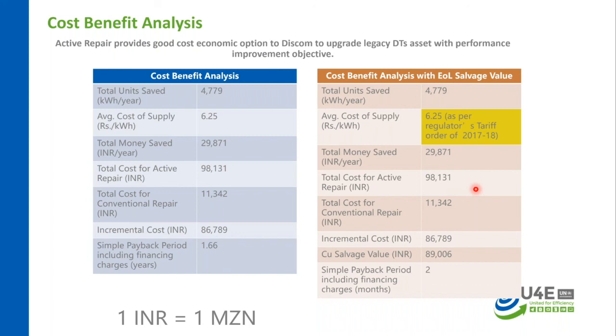But therefore, the payback period with the normal repair cost is 11,000 Mozambique dollar or Mozambique currency. And then the incremental cost due to active repair was 86,000, but the payback period was only 1.66 year. The same thing, if you consider the salvage value of the newly added materials such as copper or the steel, etc., your payback period will be just a few months.